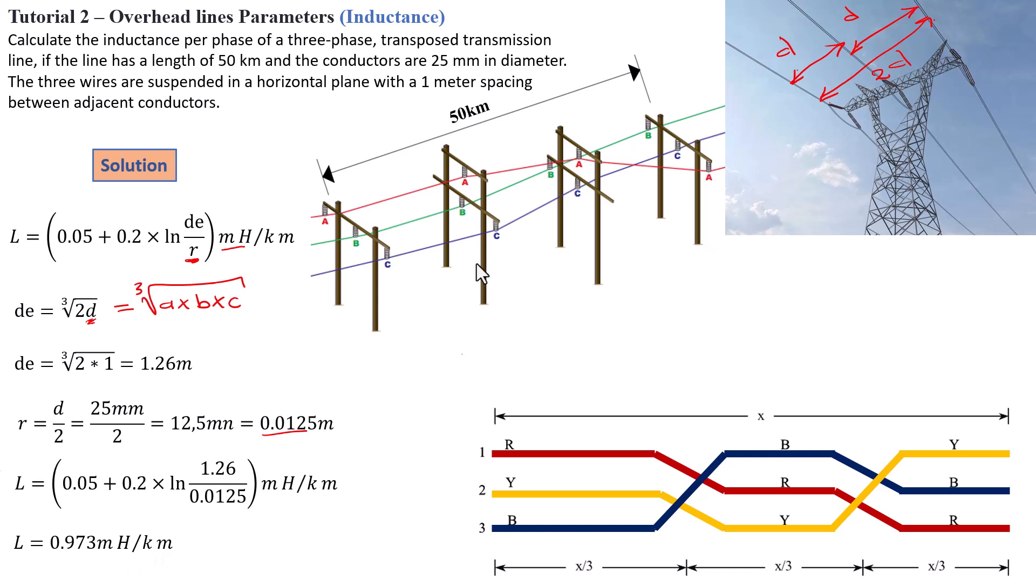Now, this basically tells us that if you're going to have this kind of configuration structure, that's the inductance that you have. So now, if your line is going to run for 50 kilometers, all you have to do is basically multiply the calculated inductance times 50 kilometers. So that will be L equals 0.973 times 50 divided by kilometer millihenry per kilometer. These will basically cancel the kilometers here and you're going to have a final inductance value of 48.63 millihenry for this line parameter here.